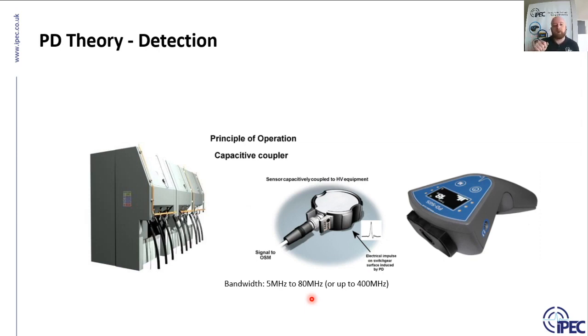In PD test equipment, the TEV sensors are often built inside, like this one here. So the head of the sensor is a TEV sensor, but you can also get them as external individual sensor types, which is what we use on our permanent monitoring systems. The sensors themselves are relatively simple. They're a capacitor. One side of the capacitor is the sensor and the other side is the switchgear. So if you get these high frequency signals occurring across the surface of the switchgear, these CCTEV sensors will be able to detect this signal.